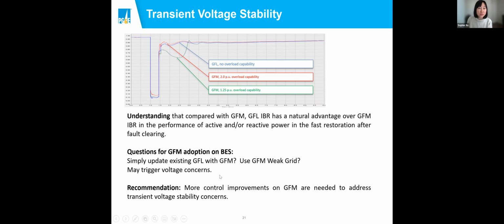And the question I would ask is, if we start to adopt grid forming inverters on BES, I heard that it could be as easy as flipping the switch on existing grid following inverters to convert them to grid forming inverters. But with this kind of voltage performance, we want to be very careful before we flip the switch, because we could see voltage concerns after we flip it.